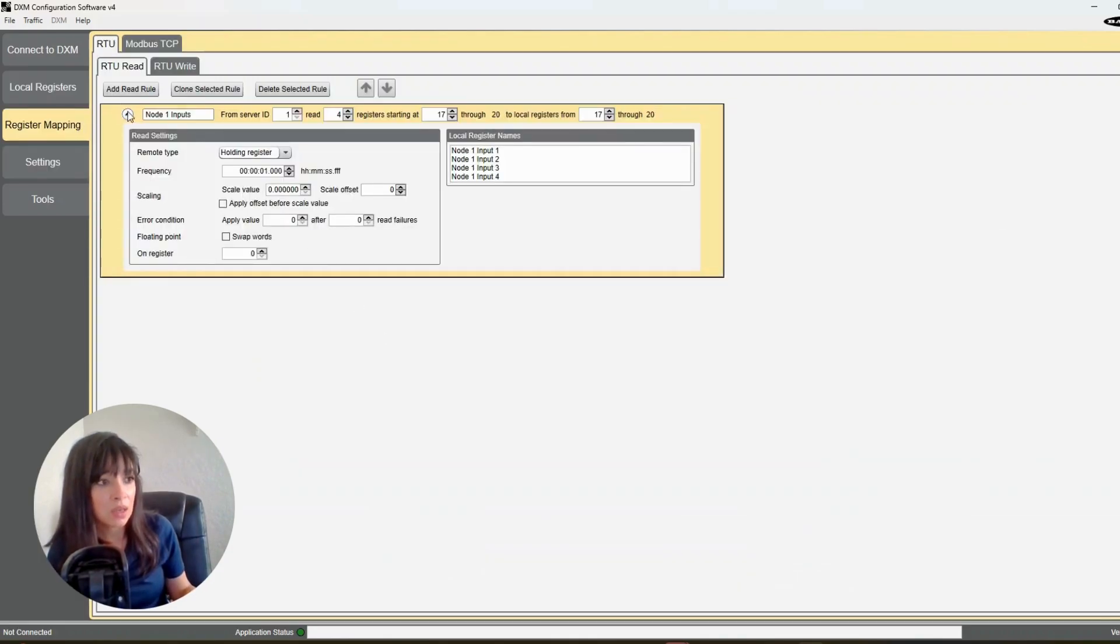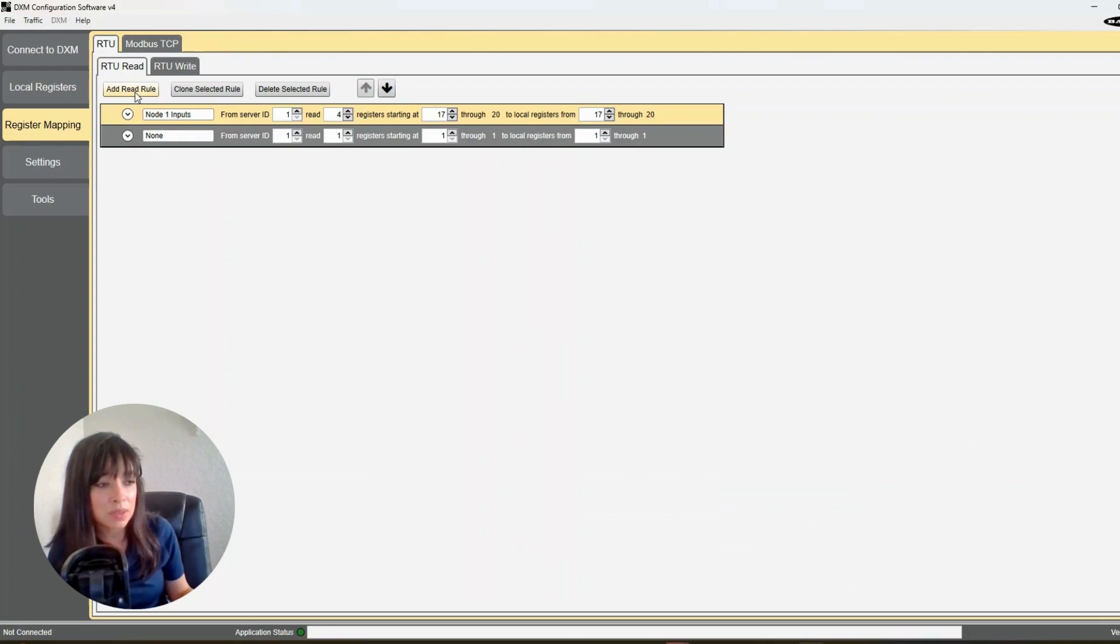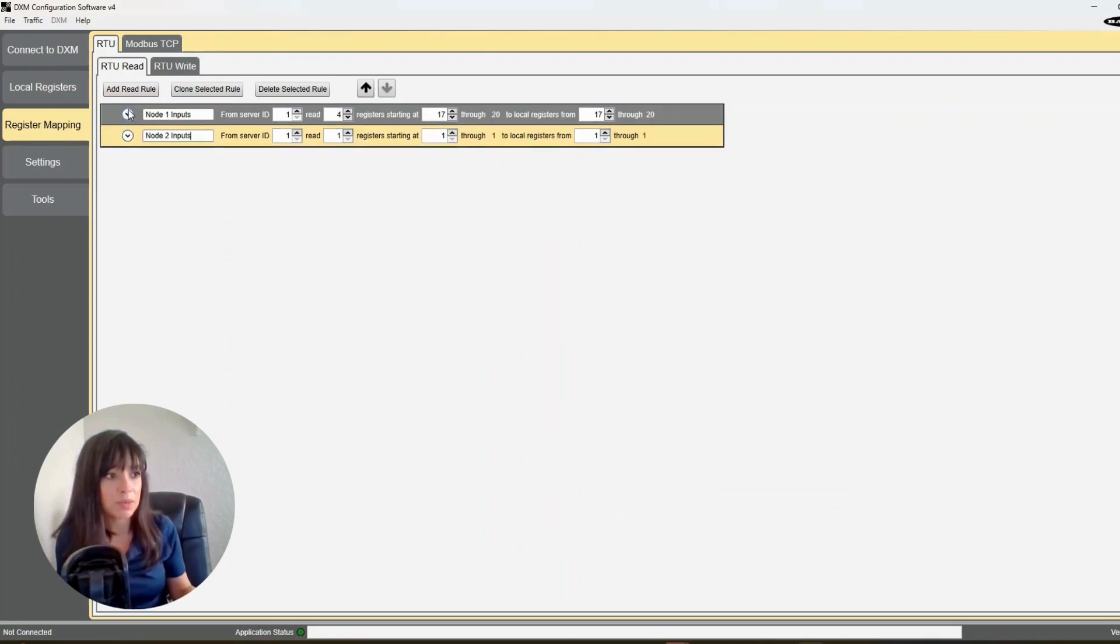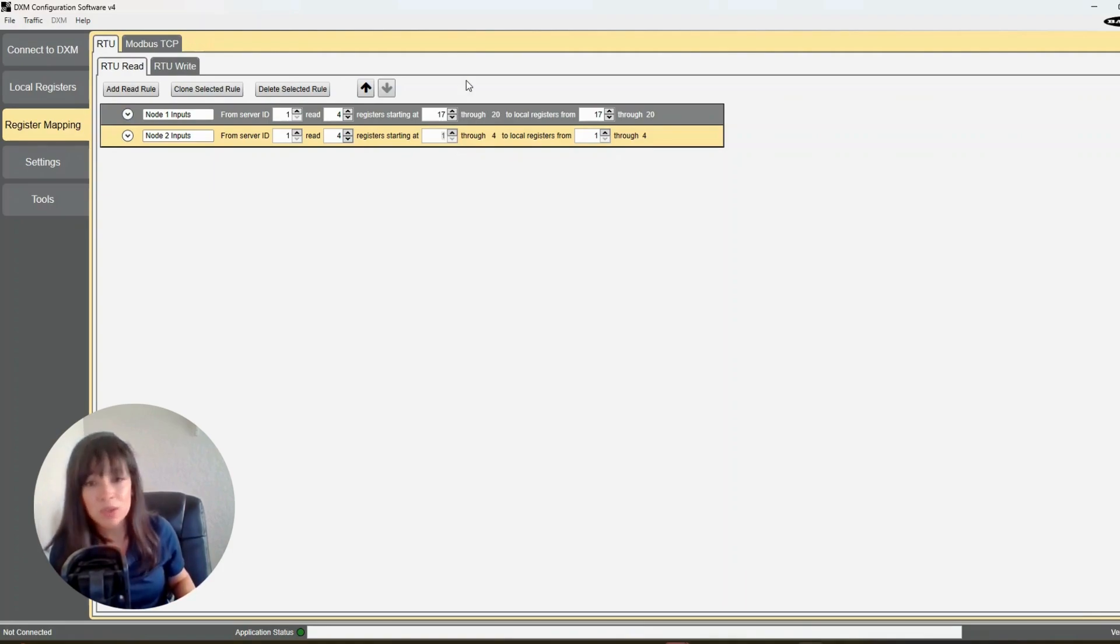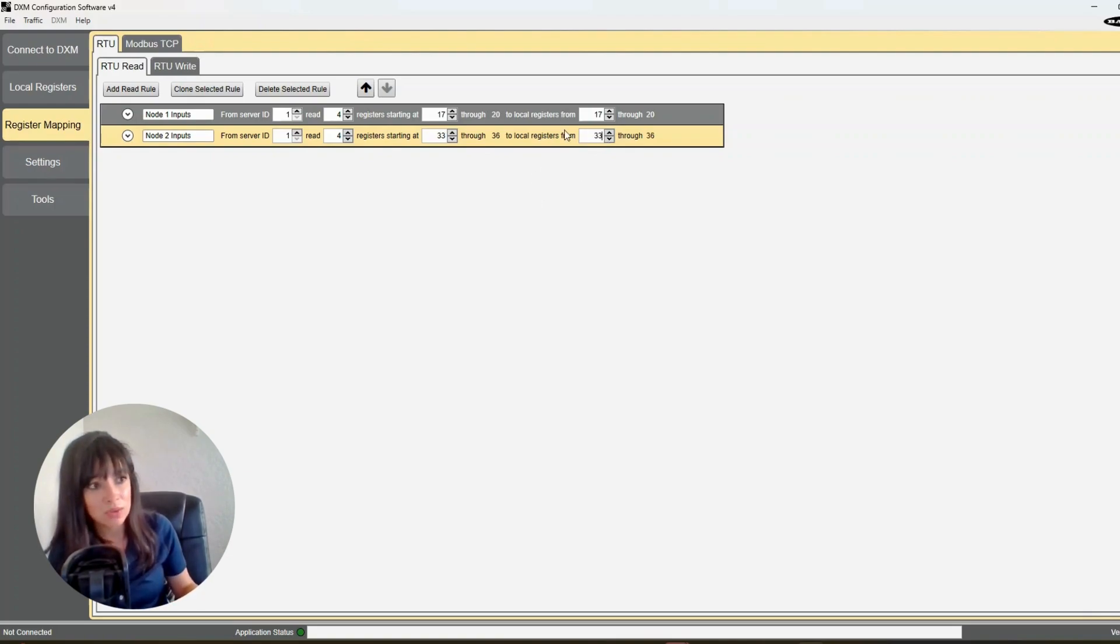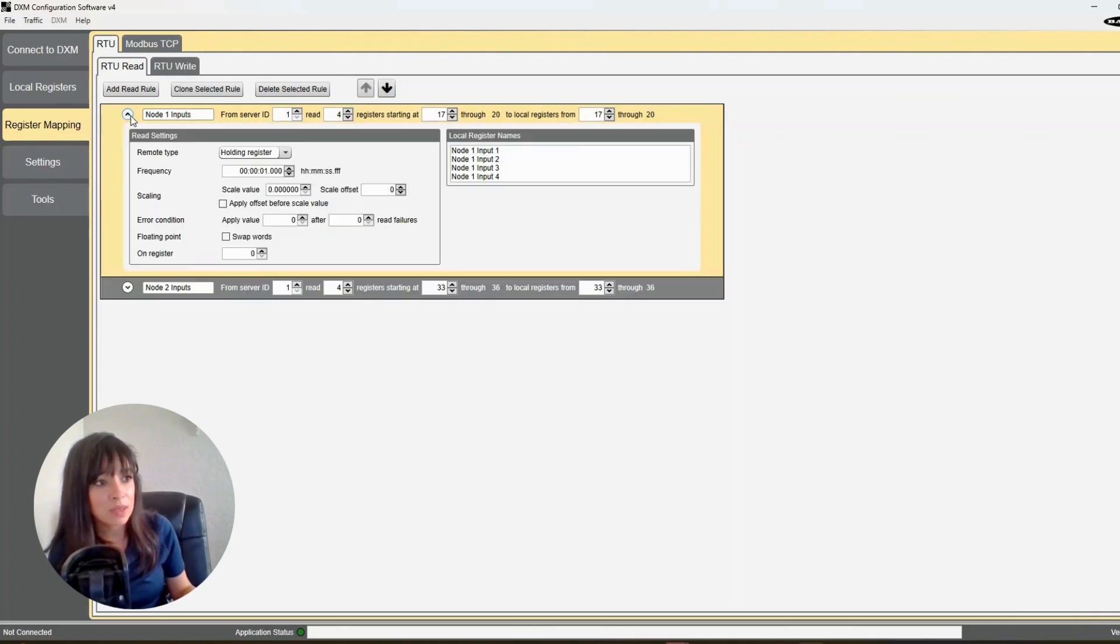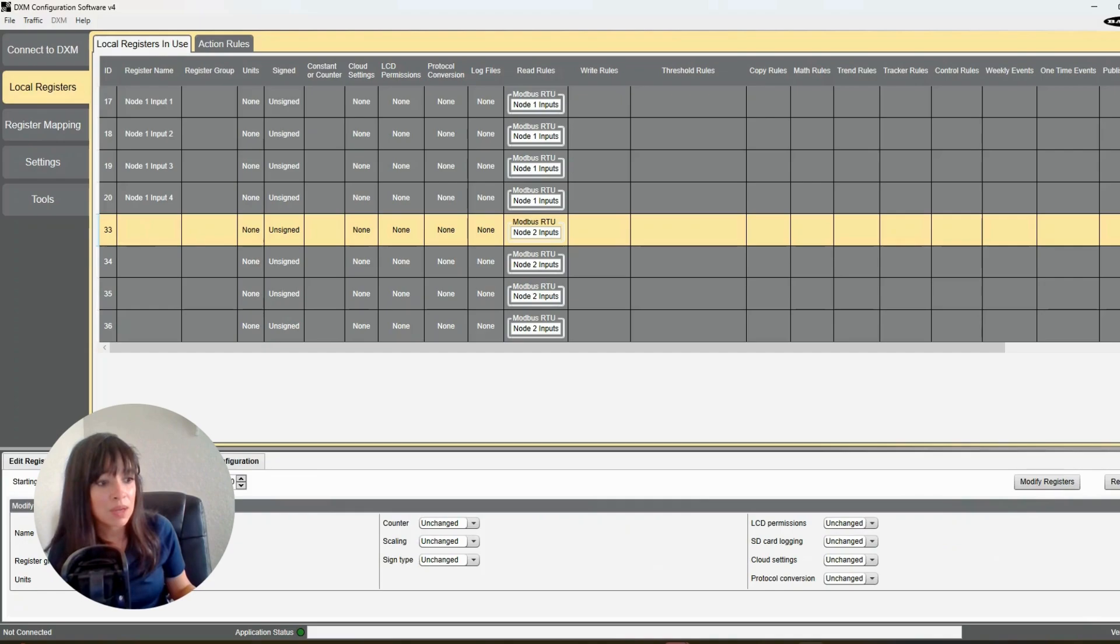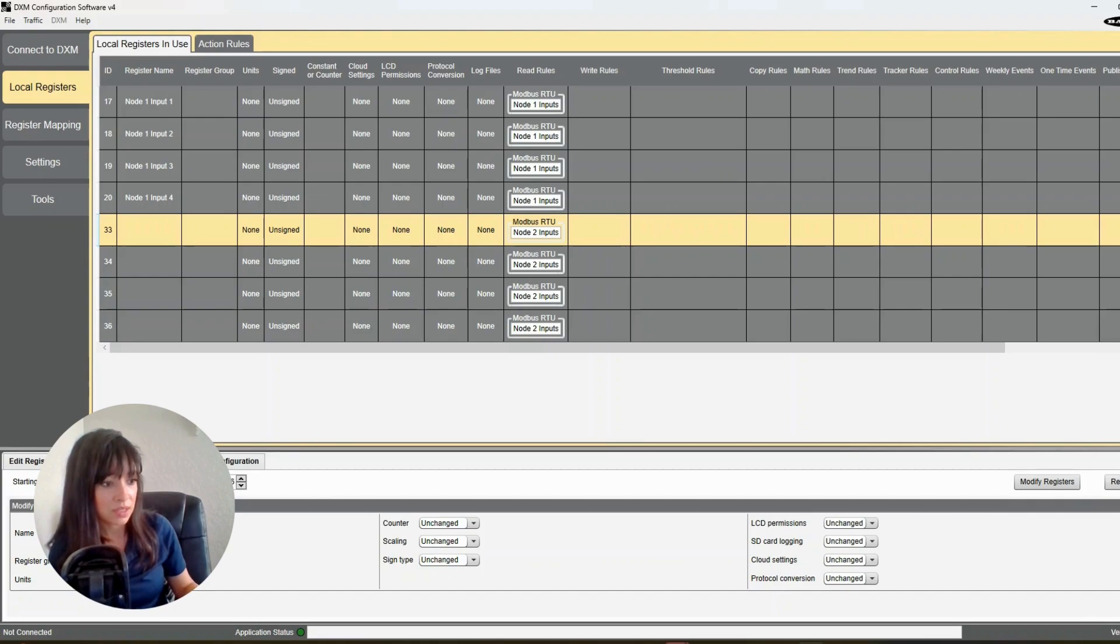Now I'm going to add another read rule for node 2. These are going to be my inputs, and all I'm going to change here is my Modbus location and my local register location. So if you do the math, it should be 33 for input 1, and I'm going to copy it into local register 33, so don't change anything here. By the way, once we name our local registers they do come up here, so we know we did it right. Go back to local registers and now I'm going to modify multiple, do the same thing that I just finished doing and give this guy some information.